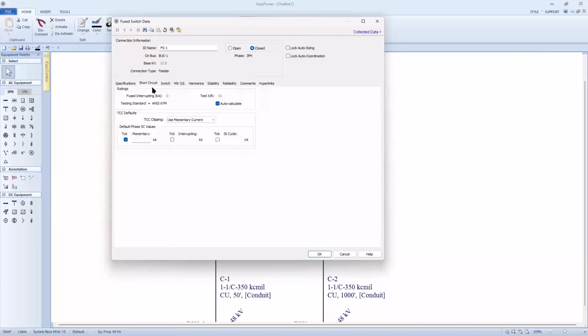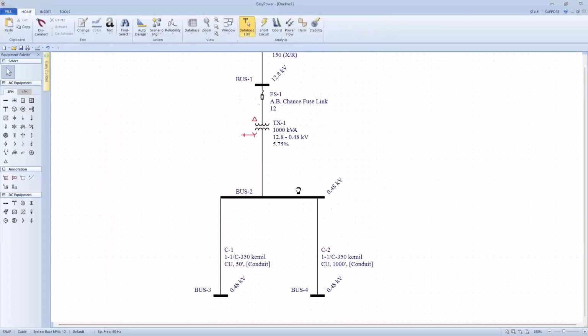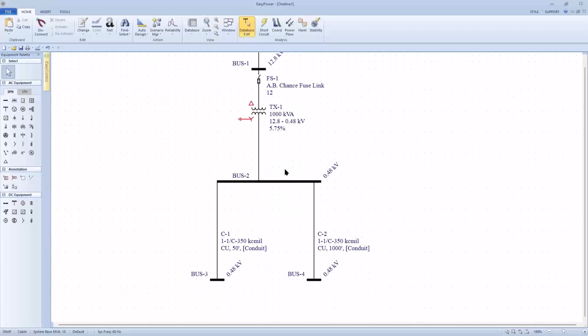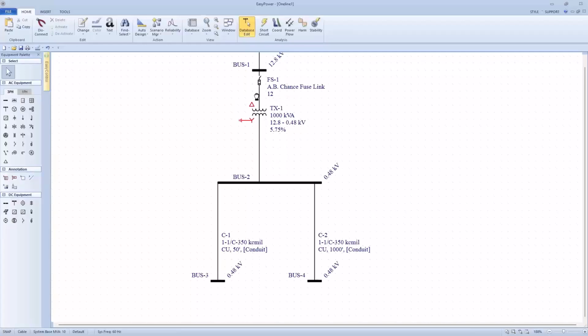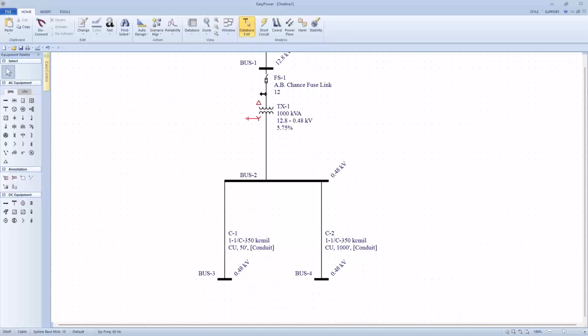Now, because I want to make sure it's connected to my device library, I go to the short circuit tab and I'm going to zero out my 15 and then auto calculate. The fact that 15 shows up, the tool's telling me, Jim, I found the part number you gave me. It's in the device library. The manufacturer tested it to an ANSI standard using symmetrical current, and the test fixture X over R was 15. The reason this is important, EasyPower is going to calculate the X over R for every bus in my system, and if anything has a protective device located in that bus, it will compensate for the difference between the test fixture and the installed element in my system.